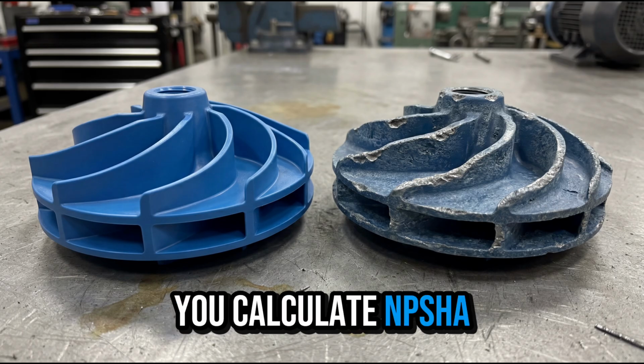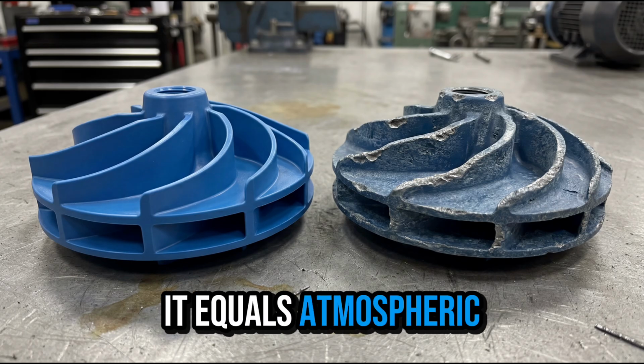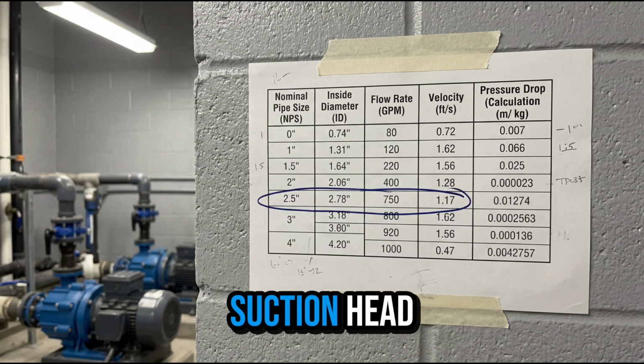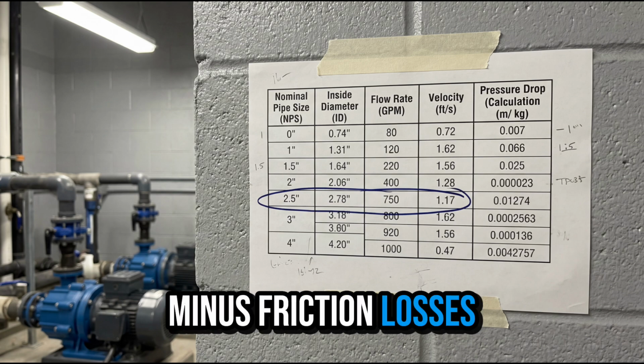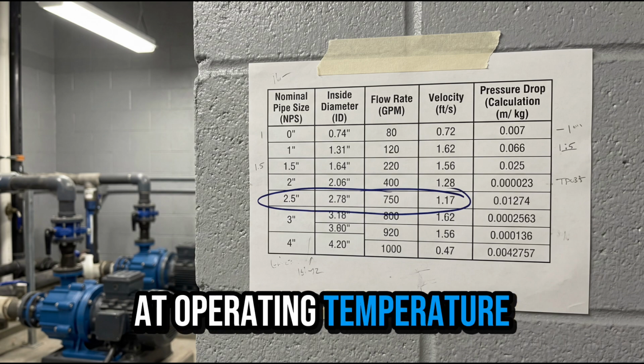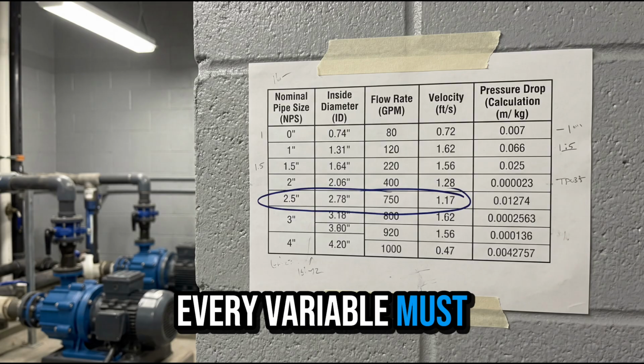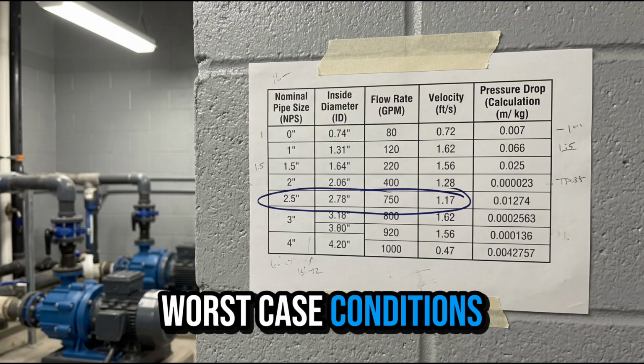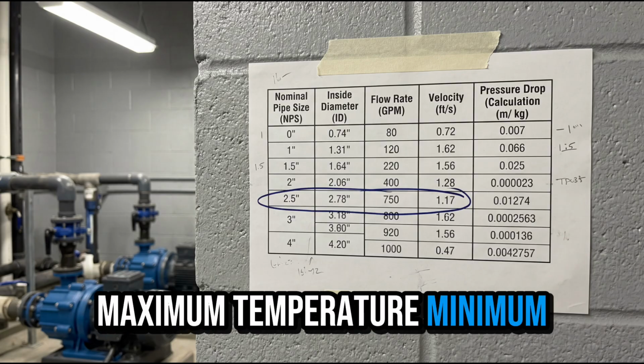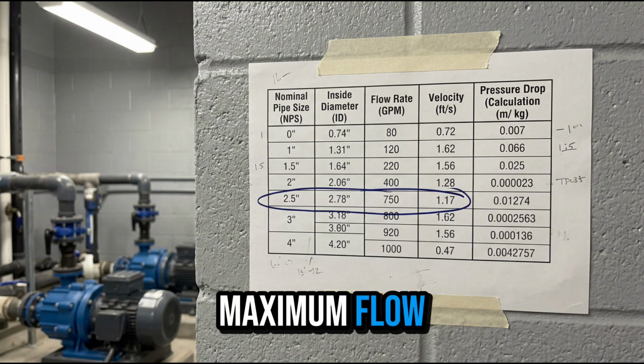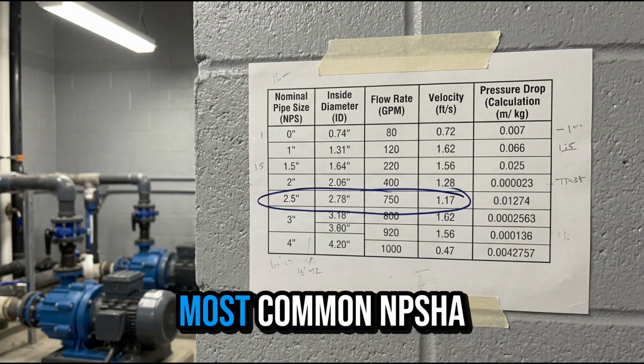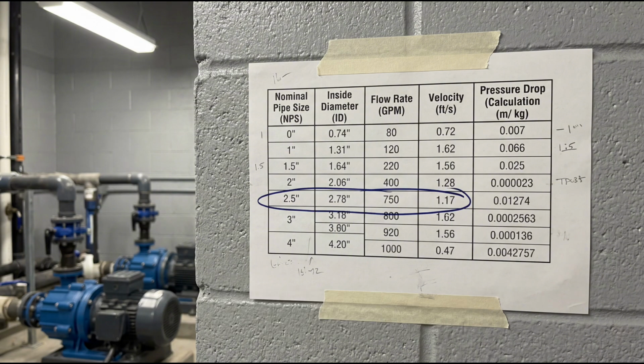So, how do you calculate NPSHa? It equals atmospheric pressure plus static suction head, minus friction losses, minus vapor pressure at operating temperature. Every variable must be evaluated at worst-case conditions. Maximum temperature, minimum tank level, and maximum flow. Now, let me walk through the most common NPSHa killers.